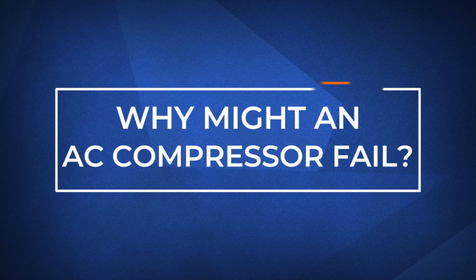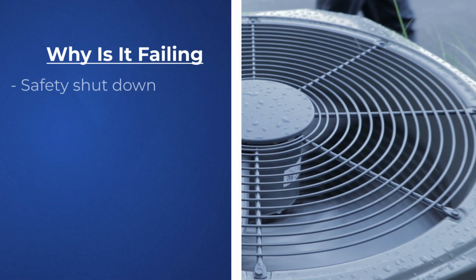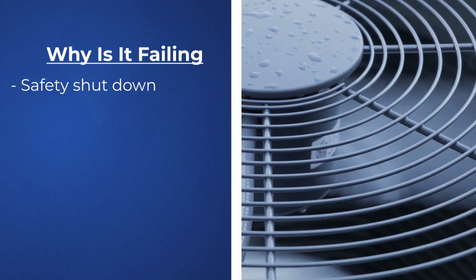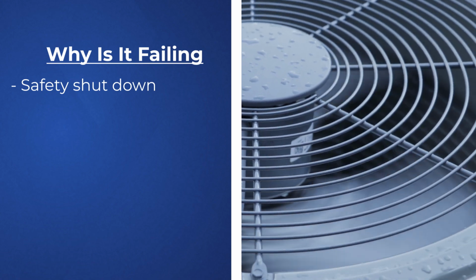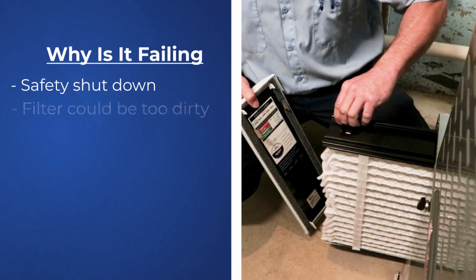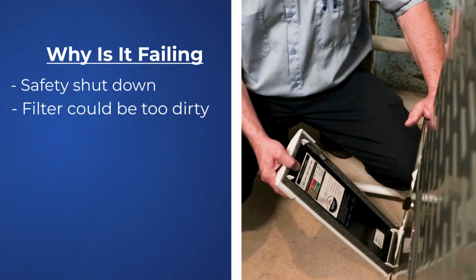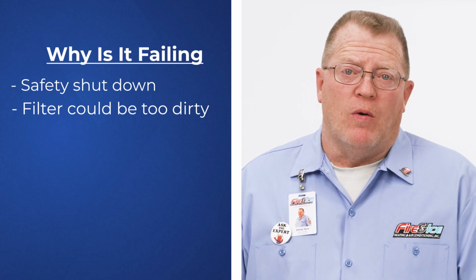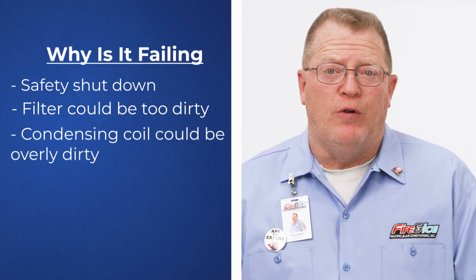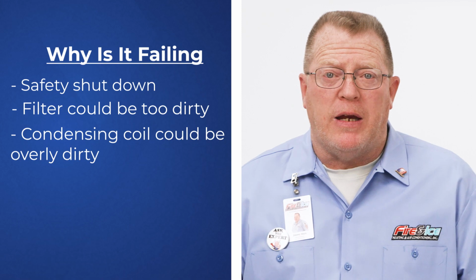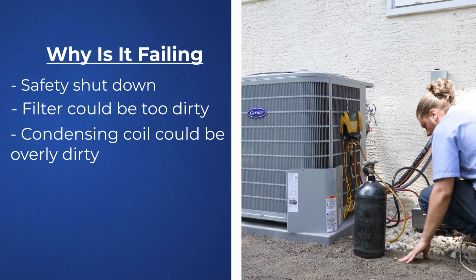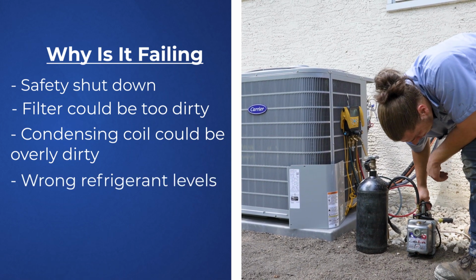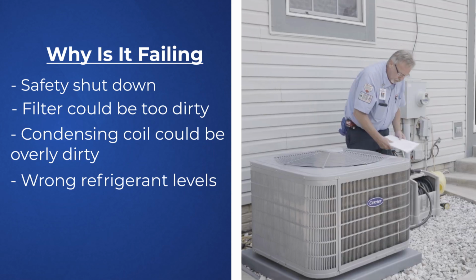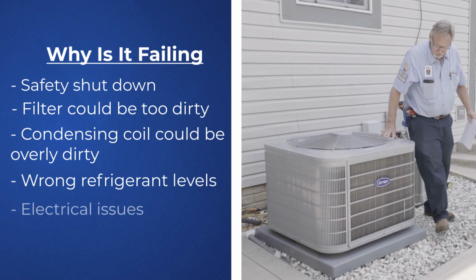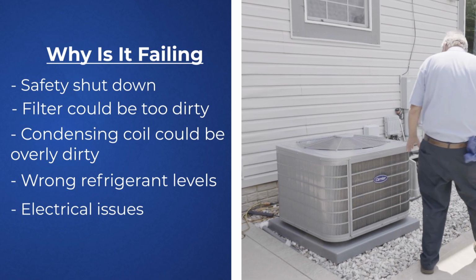There are many reasons why your AC compressor might stop working. Your compressor could be shutting down as a safety precaution if your system detects a major issue with the compressor or the condensing coil. Your filter could be so dirty that it's inhibiting the evaporator coil from working correctly. And speaking of coils, the condenser coil can become so dirty that it loses its ability to radiate heat away from the unit. Your refrigerant levels not being right can also cause the compressor to shut down. And finally, there could be electrical problems with your unit, or you could have a capacitor that's failed.